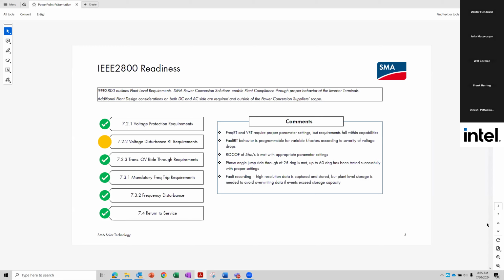Rate of change of frequency (ROCOF) of 5 Hertz per second is met with appropriate parameter settings. And Dinesh mentioned this too. The earlier IEEE 1547 requirements of anti-islanding protection made the parameters rather sensitive to ROCOF. But if you are turning off anti-island protection on these transmission connected projects, we can open up the ROCOF settings. The 5 Hertz per second is quite easily met. Phase jump ride-through of 25 degrees is the requirement in the standard. In our hardware in the loop system, we have tested our equipment up to 60 degrees.